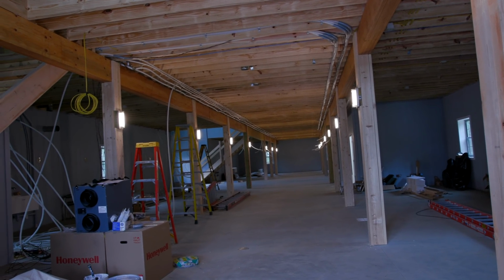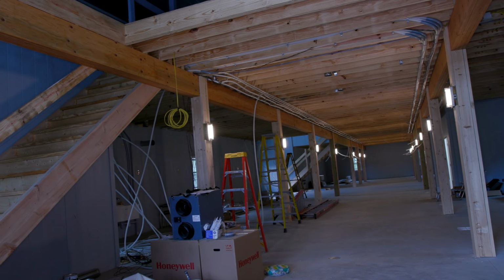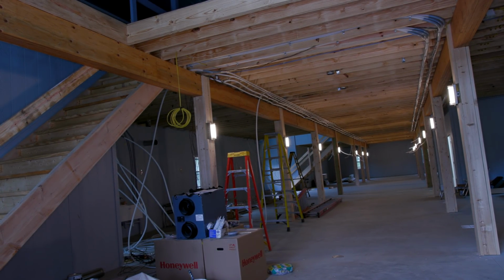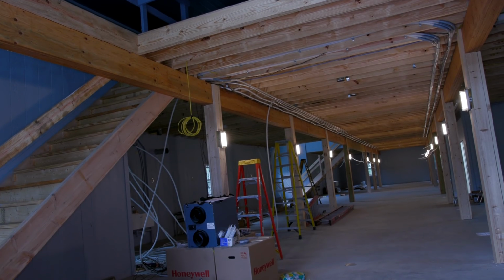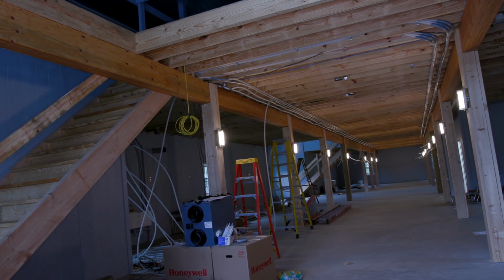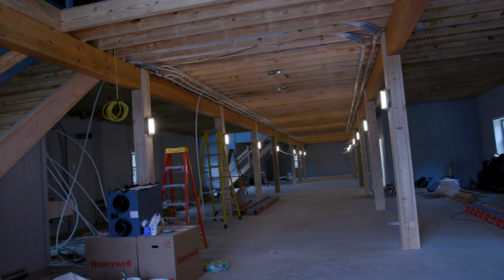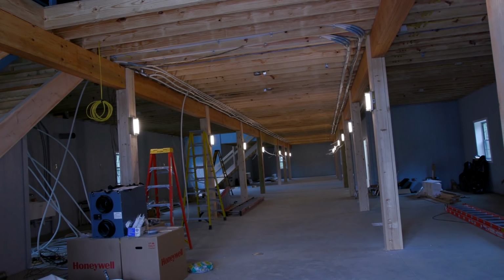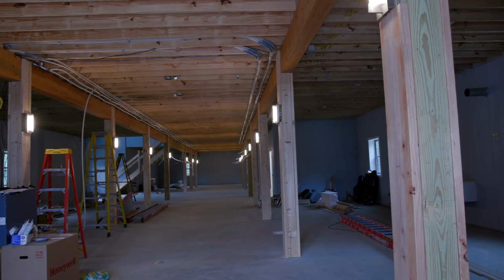Finally the electricians came over, and it happened while they were here. And it happened a couple times, so they were finally able to diagnose it. We have two outlets outside that are going to be exterior outlets. The problem was that since those were also unfinished, the wind would blow and one of the exposed tips, don't ask me why there's exposed tips on those wires, would hit the metal siding of the building and would just arc and trip the breaker. So outside there's these two little burnt marks in the siding where that kept on happening.